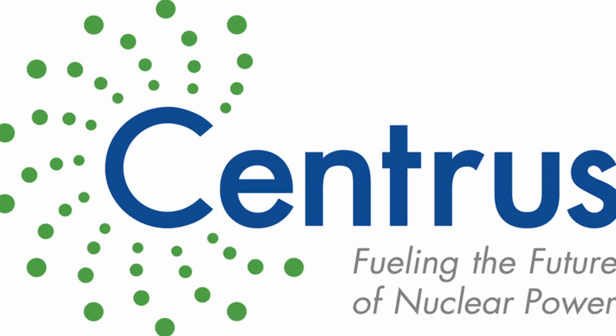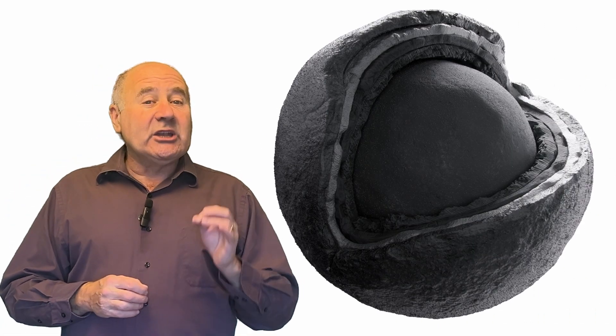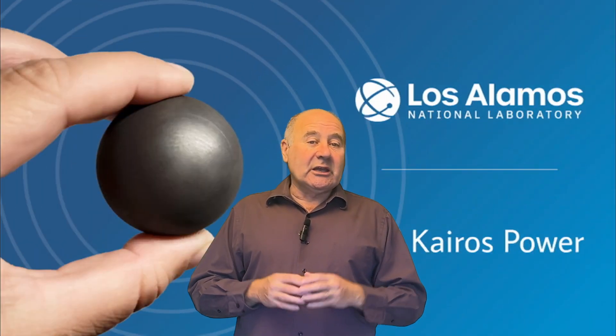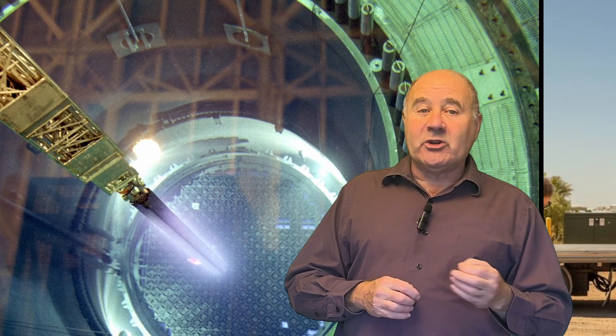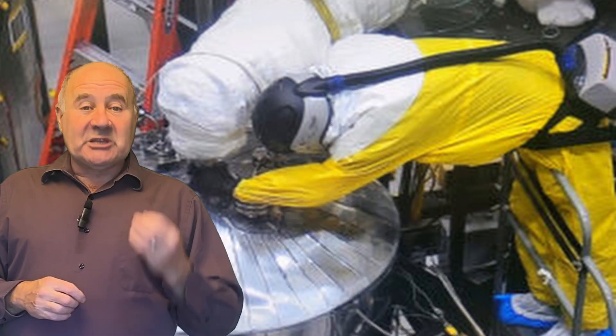There's a U.S. company, Centrus Energy, working on developing a supply chain for that fuel, but their roadmap is a risk for all reactors relying on it. The protective layers of TRISO particles remain intact up to very high temperatures, ensuring safety in the case of coolant loss. The TRISO particles will be combined into golf ball-sized pebbles at a facility at Los Alamos National Laboratory, and these pebbles have another layer of protection on them. Another unique element of Kairos' approach is their coolant. Almost every reactor built to date uses water to carry away the heat — water not only carries away the heat but also slows the neutrons, and slow neutrons react more readily with uranium-235. Kairos chose molten fluoride salt coolant, which doesn't slow the neutrons, so they include graphite in their fuel particles as a moderator. So it's a thermal or slow neutron reaction where an exotic liquid carries away the heat.